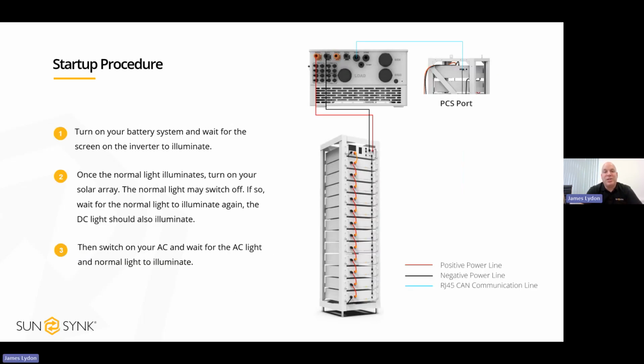Okay, so the startup procedure. This applies to all of our inverters, whether it's a 3.6 kilowatt or a 50 kilowatt high voltage. What we always recommend is, you've got the PV connected, so you've got your MC4s connected, the grid's connected, the battery's connected. Everything's off, so everything's isolated. We always recommend leaving the grid isolated, leaving the PV isolated, and first just introduce the power from the batteries.